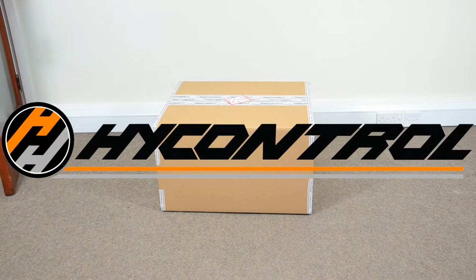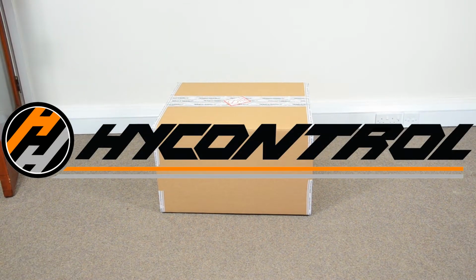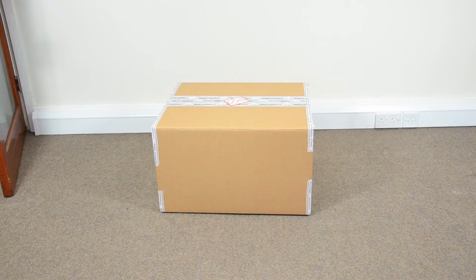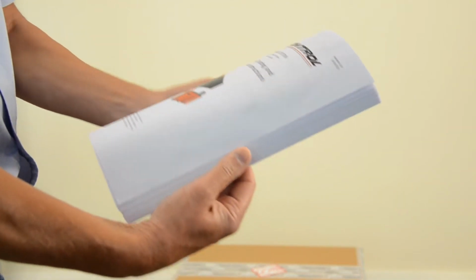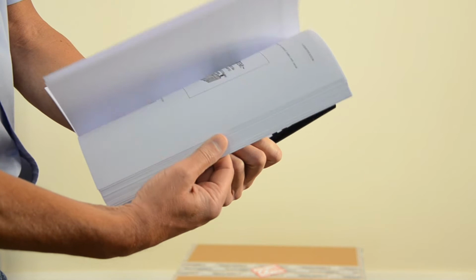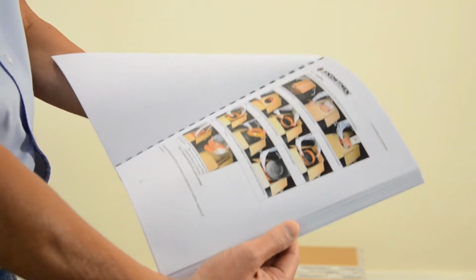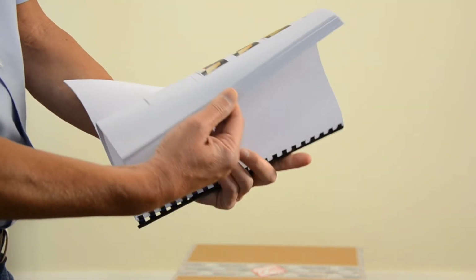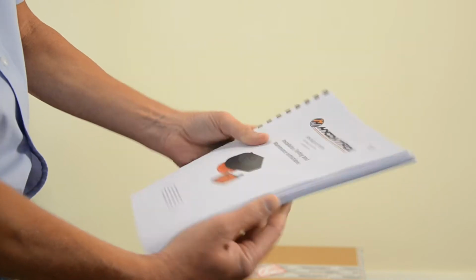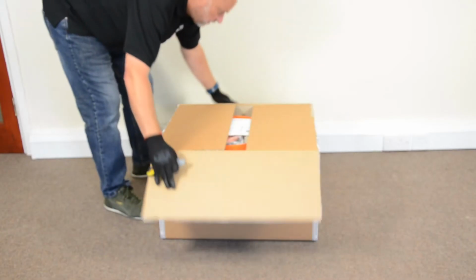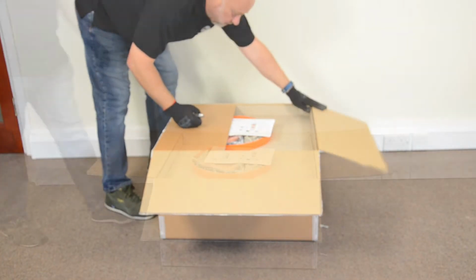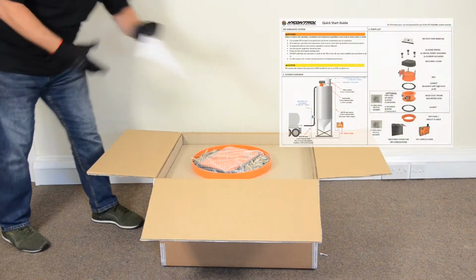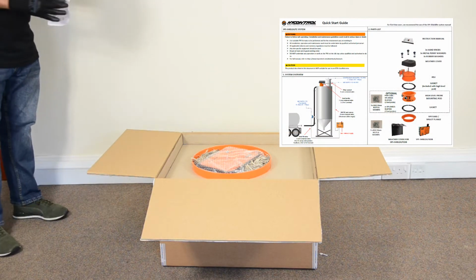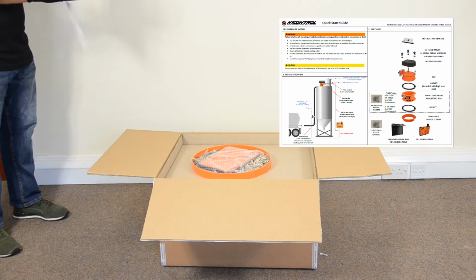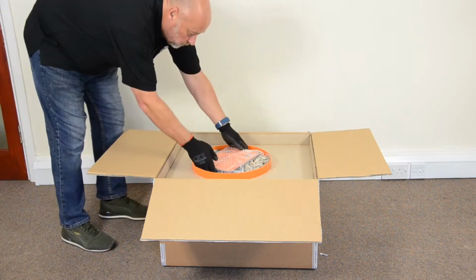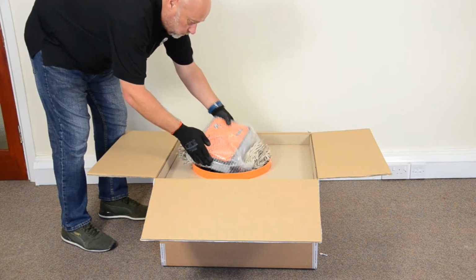We're going to talk through the unpacking and assembly of the SHIELD Lite silo protection system. We recommend users print out a copy of the full manual for their reference, as this provides in-depth information. Carefully open the box. Inside, you will find the Quick Start guide on the top, which you will need to refer to for wiring, so put this to one side. Then remove the display panel and put that aside.